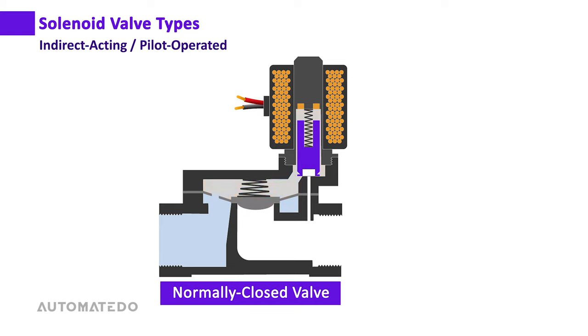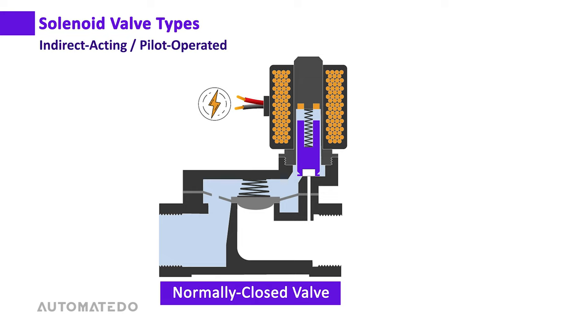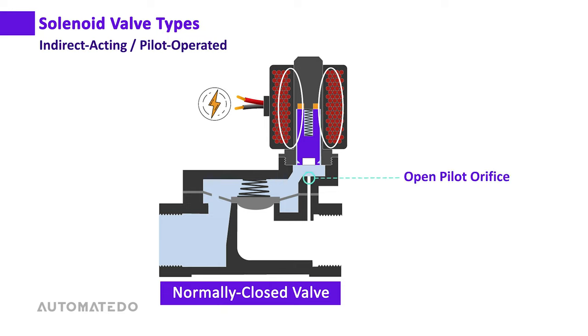The upper chamber is connected to the low pressure port by a small channel called a pilot orifice, which the plunger blocks in the closed position. When the solenoid energizes, the electromagnetic field pulls the plunger upwards, opening the pilot orifice. Pressure begins relieving from the upper chamber, making the upward force below the diaphragm stronger than the downward force above it.